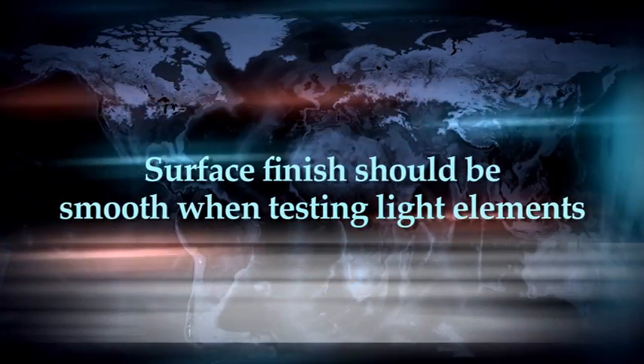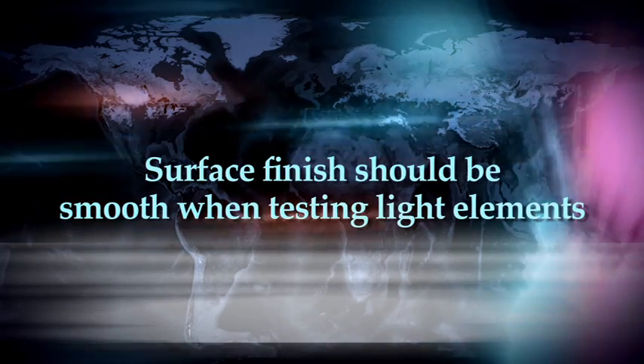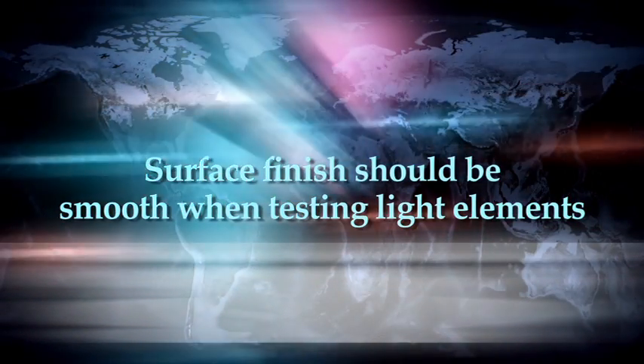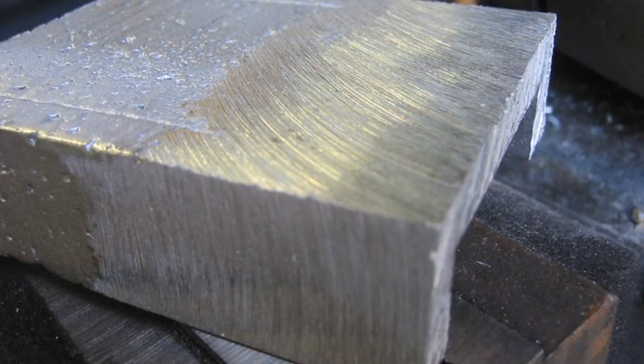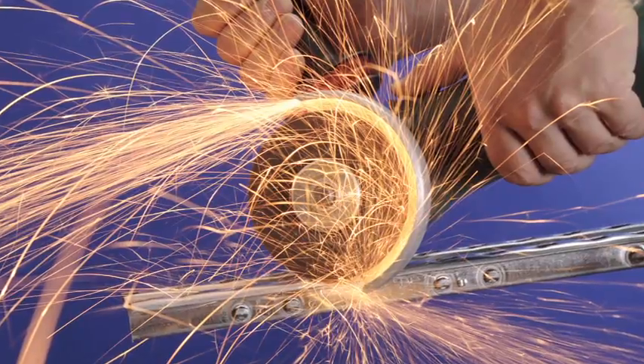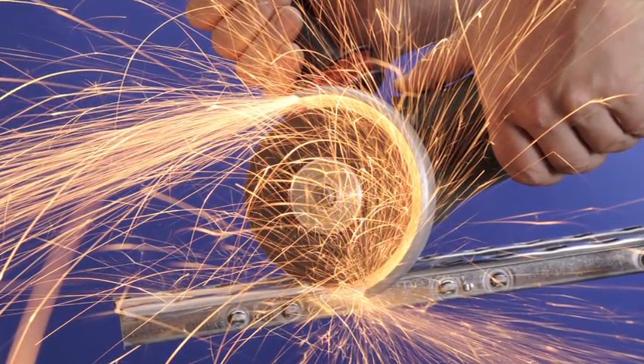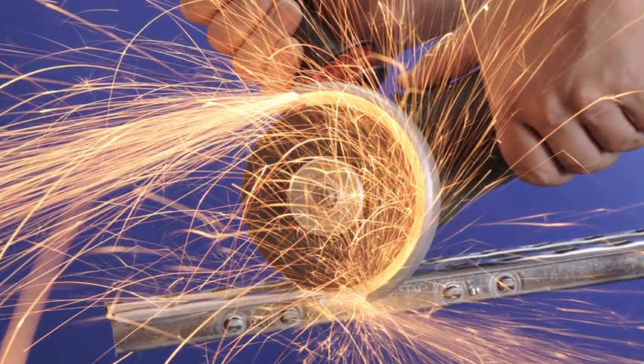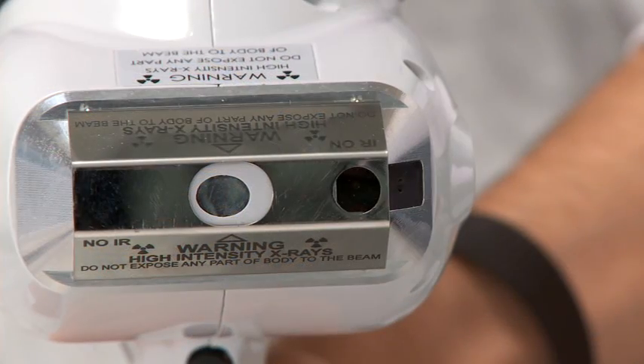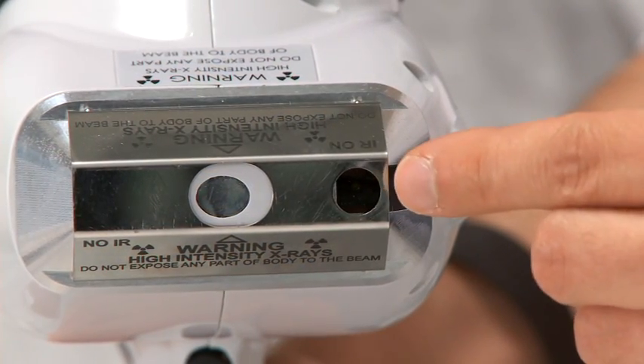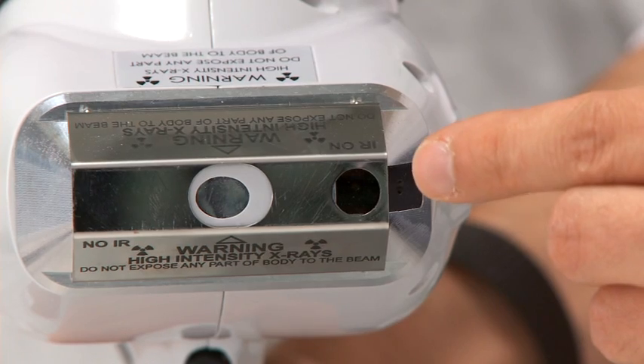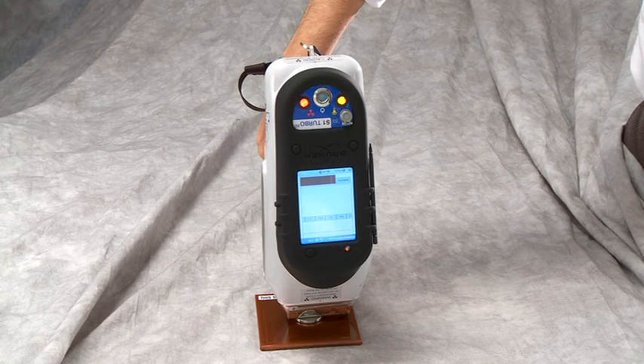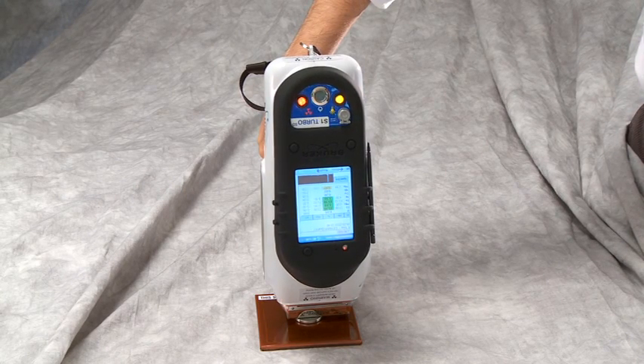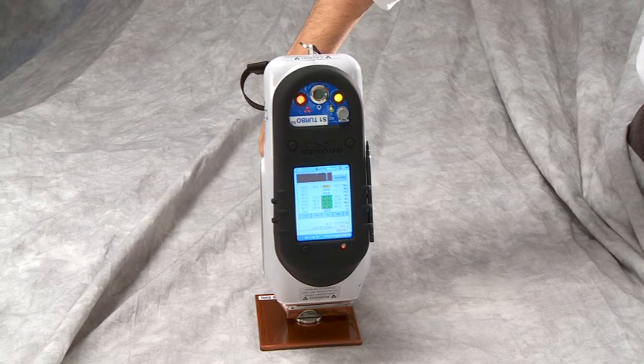If light elements like silicon and aluminum are being measured, the condition of the surface finish is even more important. In this case, heavy cutting marks and coarse scratches will interfere with the measurement. If necessary, a grinder with 60 grit abrasive can be used to smooth the surface, providing a suitable surface for measurement. The IR sensor in the front of the analyzer is an important part of the safety circuit. This sensor detects reflected infrared radiation and confirms that a sample is in place in front of the analyzer.